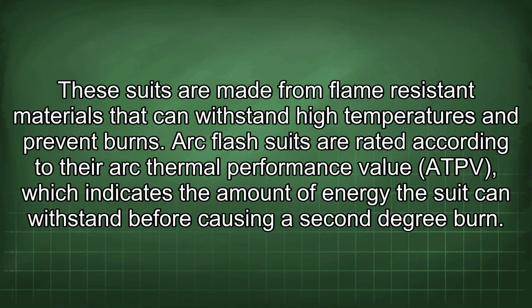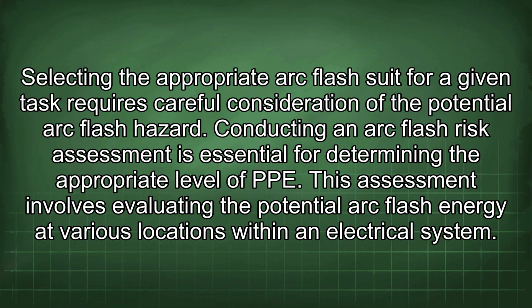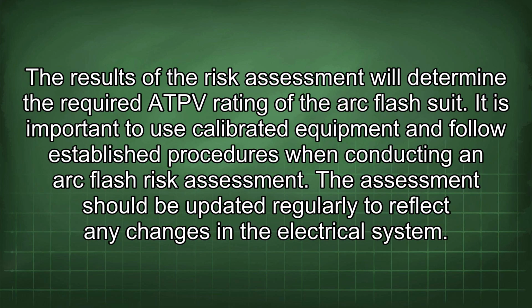Arc flash suits are rated according to their arc thermal performance value (ATPV), which indicates the amount of energy the suit can withstand before causing a second-degree burn. Selecting the appropriate arc flash suit for a given task requires careful consideration of the potential arc flash hazard. Conducting an arc flash risk assessment is essential for determining the appropriate level of PPE. This assessment involves evaluating the potential arc flash energy at various locations within an electrical system. The results of the risk assessment will determine the required ATPV rating of the arc flash suit.